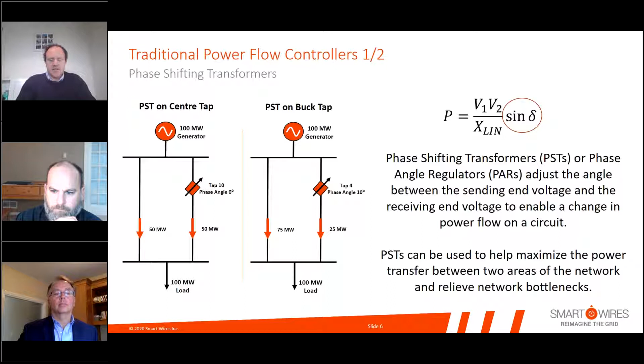PSTs are used across the world to maximize transfers between 2 different areas of the network and relieve bottlenecks. And you can see on the left hand side, there's a diagram here showing that when the PST is on center tap, so there's no phase angle across the PST at all, you've got an even distribution of power across the 2 circuits. But as you tap that, or change the phase angle on the PST, you buck power or push power off it, or you can go to a negative phase angle here and pull power onto the line that the PST is connected to.